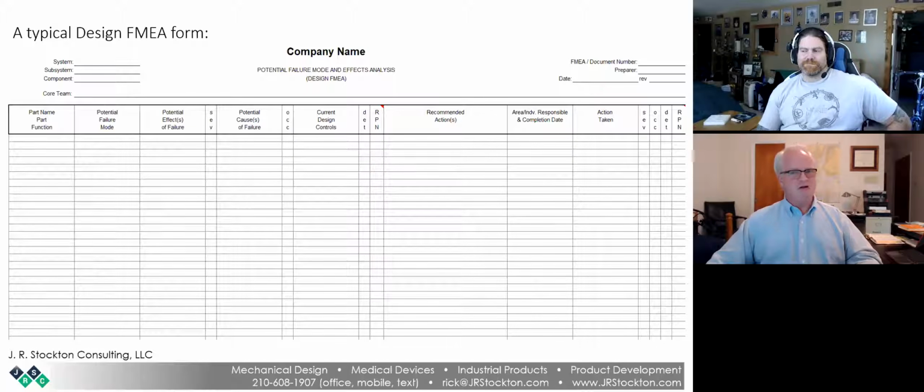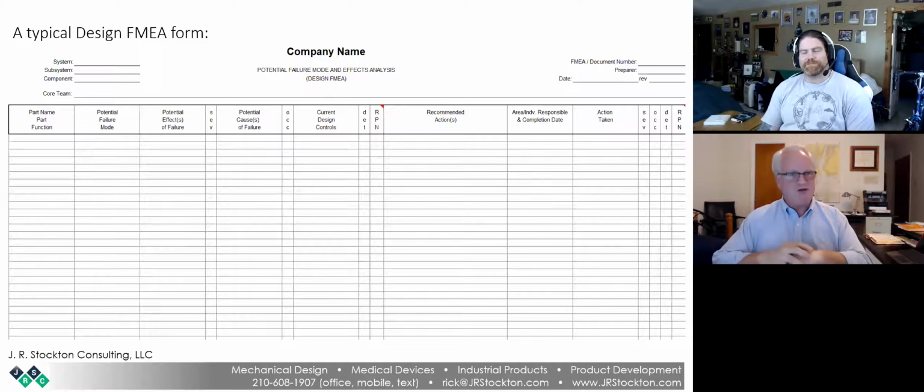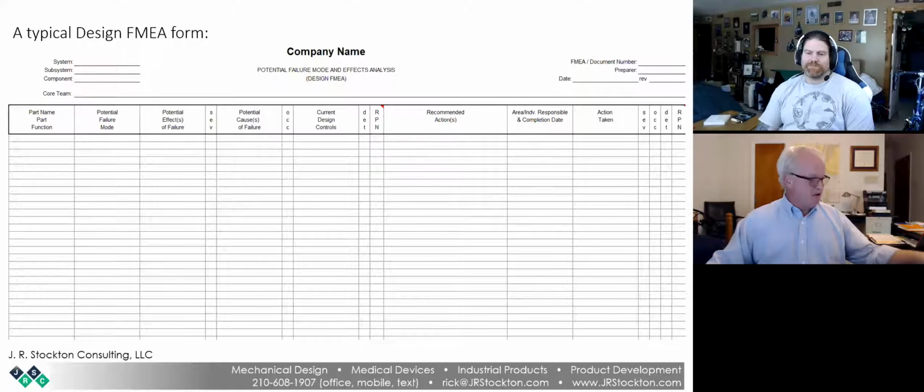So what you do is you put it into some kind of order according to a succinct set of rules and according to a fixed perspective, and you lay that out for them, and you send that to them the night before. They all get to look at it, and they all show up with red line versions, and you get to the facts so much quicker. And you end up using less than a day to go through a long FMEA, maybe only 2 or 3 or 4 meetings to get through an entire thing from nowhere.